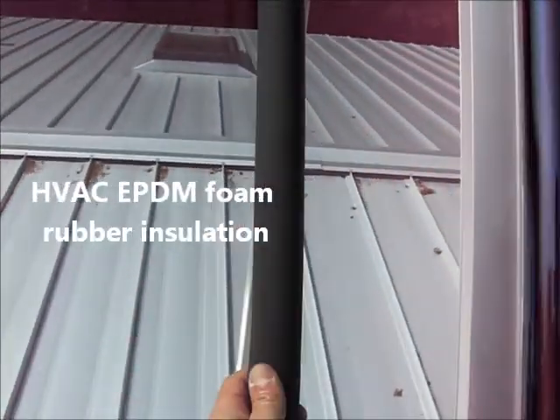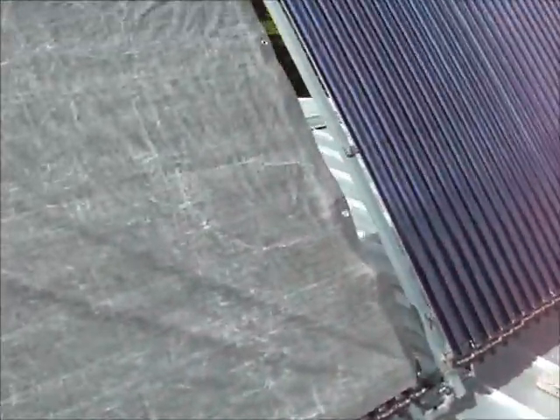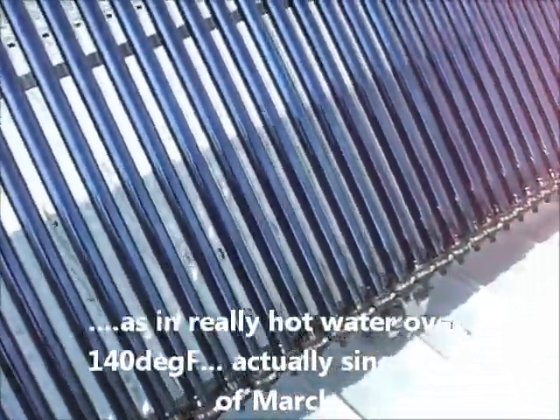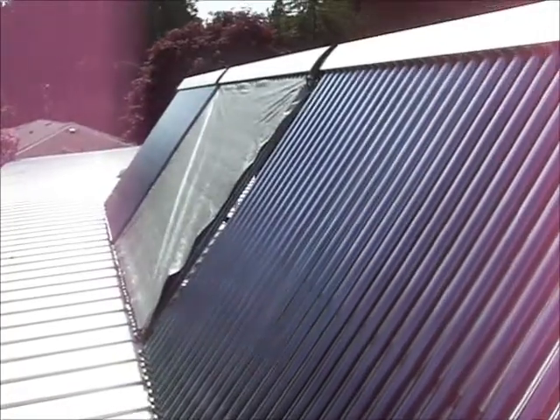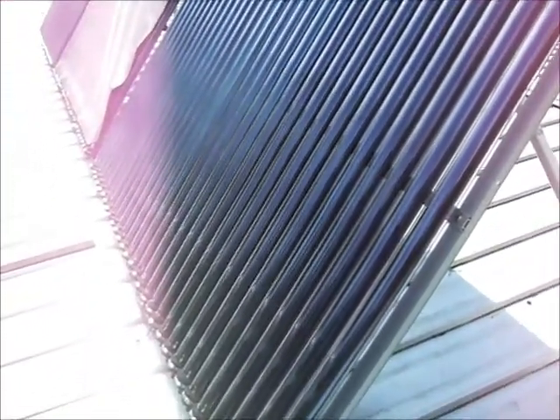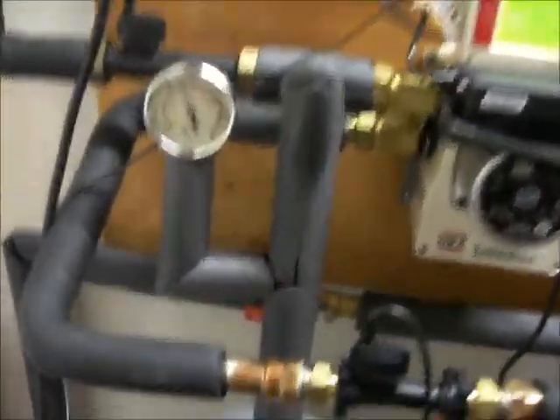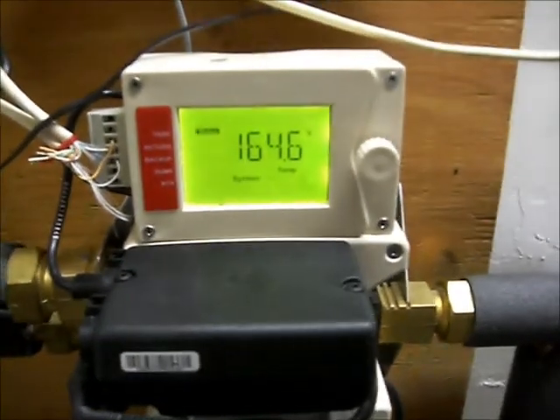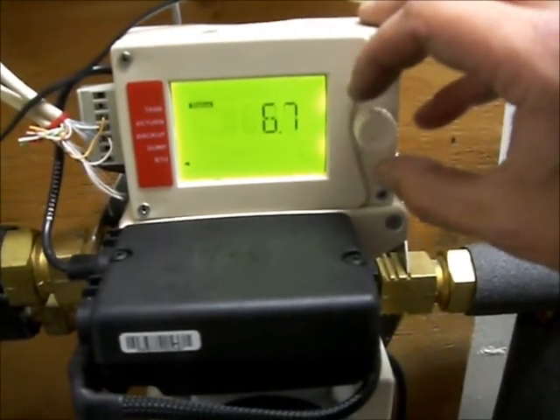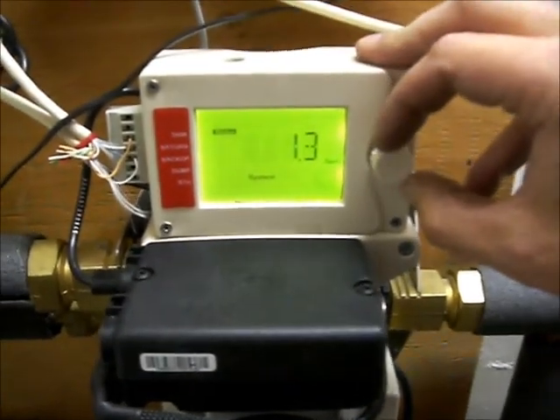The insulation is holding up really well — the EPDM stuff — and we've had hot water now for about a month and a half at least, over 140–144°F on average. I'll pop downstairs now to show you what the solar block is telling us. Downstairs, it's showing about 12.5 PSI in the system, 164.6°F up on the roof, and the return temperature — after it comes out of the solar tank — is 153.6°F. We're currently doing 1.3 gallons per minute.